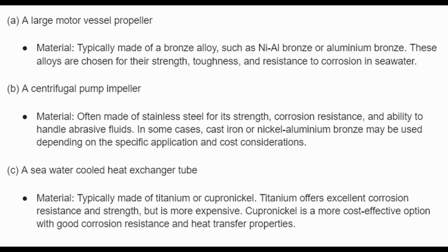C. A seawater cooled heat exchanger tube. Material, typically made of titanium or cupronickel. Titanium offers excellent corrosion resistance and strength, but is more expensive. Cupronickel is a more cost-effective option with good corrosion resistance and heat transfer properties.